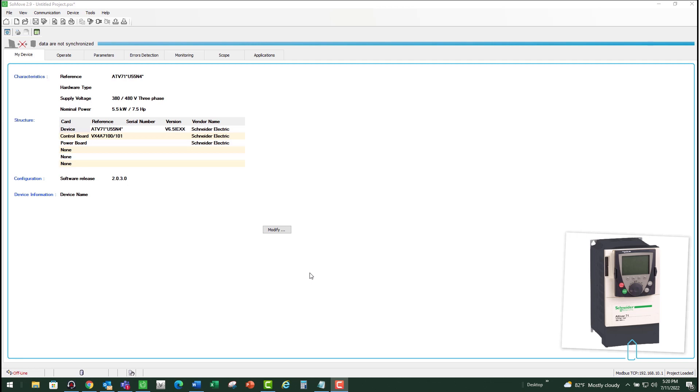There are multiple causes to OBF faults and we're going to discuss them individually. If the drive trips on OBF fault while starting, then we need to check the catch on the fly parameter and make sure it's enabled.